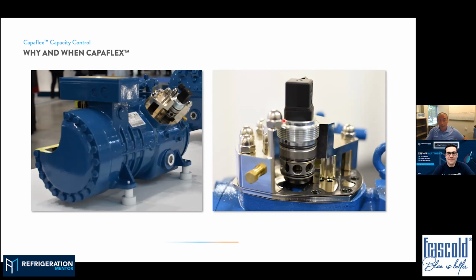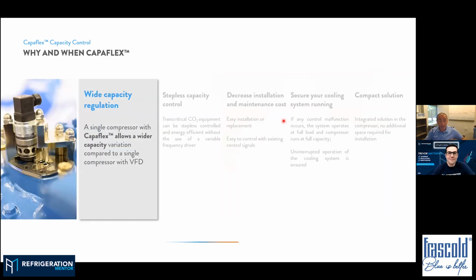We'll see in a second why and when Capaflex makes sense in a CO2 system. In a single compressor, we can reach a wider operating range than with a VFD. Typically a VFD can regulate down to maybe 25-30 hertz. If the maximum is 60, that's probably 50% of capacity, or if it's 70, it's probably 40-45% of capacity. This system will allow going as low as 20%.